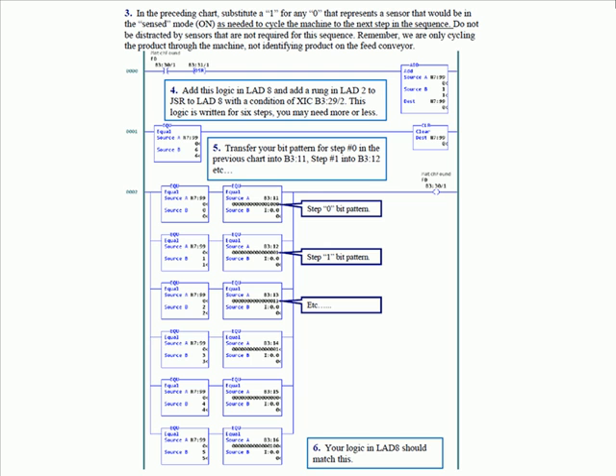This logic we added — and we're going to eventually compare, no pun intended, this to the sequencer compare instruction. Basically it's looking for a bit pattern to match what you have said needs to be matched to go to the next step. So if you look at the first rung, we have the found bit b3 30 slash 1, a one-shot rising — because we need a one-shot to prevent the add instruction. In this case this might work without it, but don't try it. The one-shot is to prevent the add from continuing to add every program scan as long as the found bit is true. So you're incrementing N7:99, which would be like the position word in a control data type.